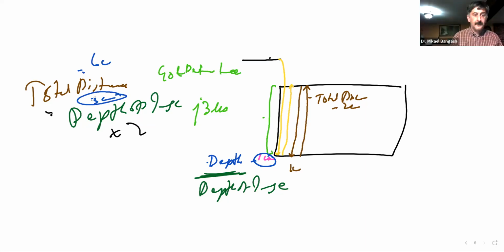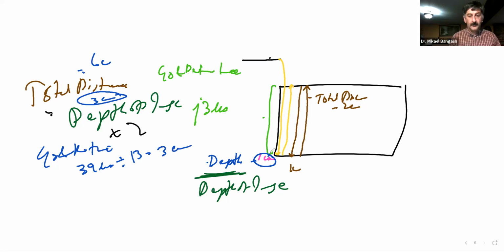Or you may determine that the depth of image was 3 centimeters because your go and return time, for instance, is given as 39 microseconds. That means it takes the sound wave or pulse 39 microseconds, that's your go and return time. So the only thing you have to do is divide this 39 microseconds by 13, and that will give you the depth of the reflector, or the depth of your image, which was 3 centimeters. But then the total distance that the sound traveled, going to that reflector and coming back, was going to be 6 centimeters.